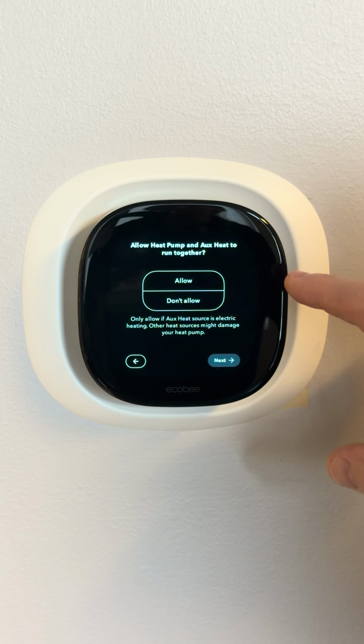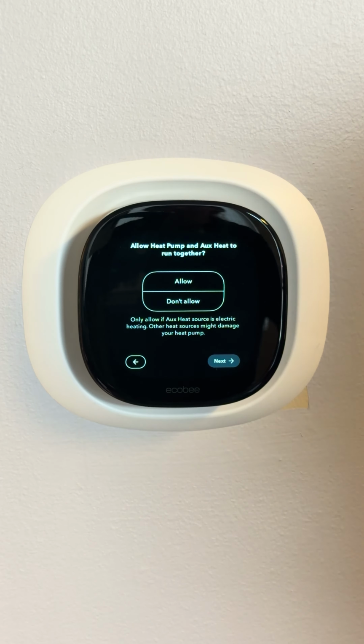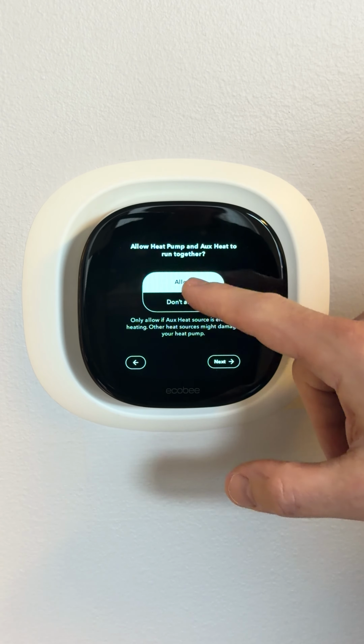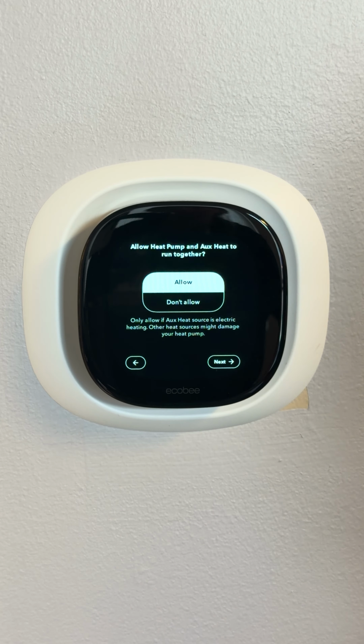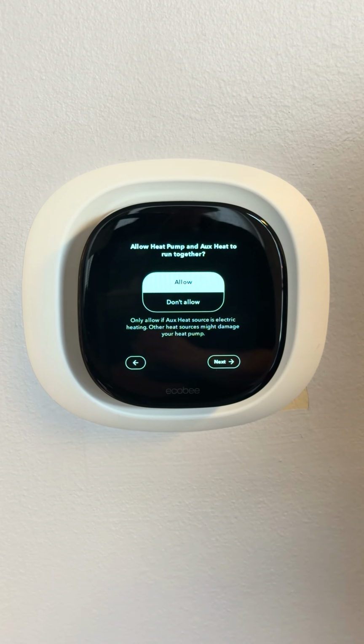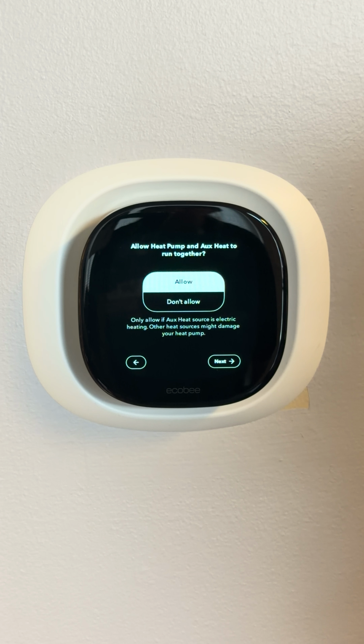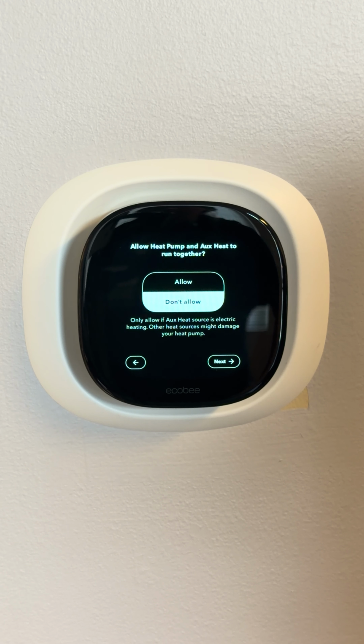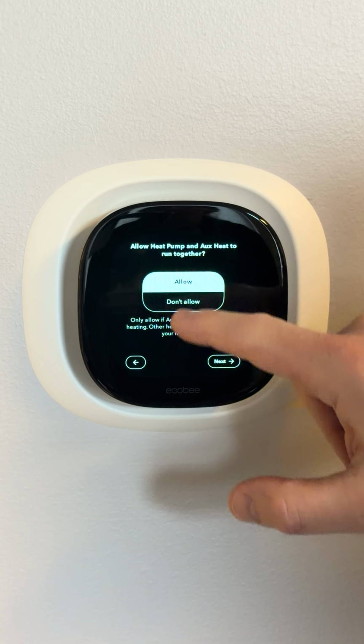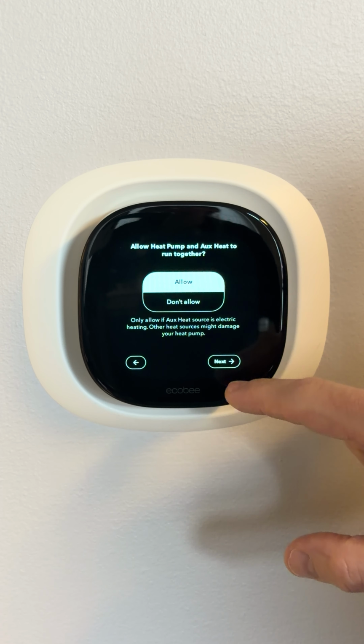We do want the heat pump and the auxiliary to run at the same time, as long as the aqua coil is installed on the discharge side of the air handler. That will allow the air to be preheated by the heat pump and then topped off by the aqua coil. If the aqua coil has been installed on the return side, make sure that you do not allow this. So since we're on the discharge side, we're going to hit allow.